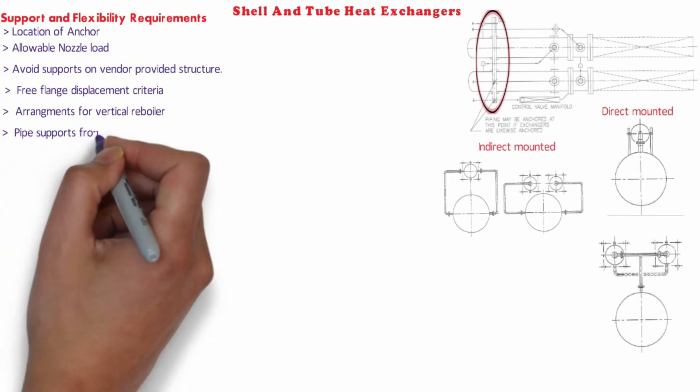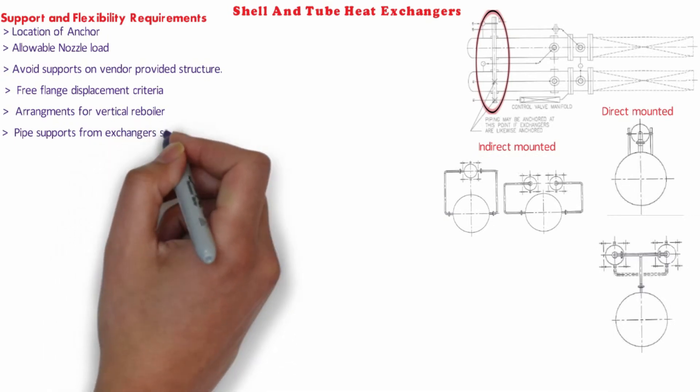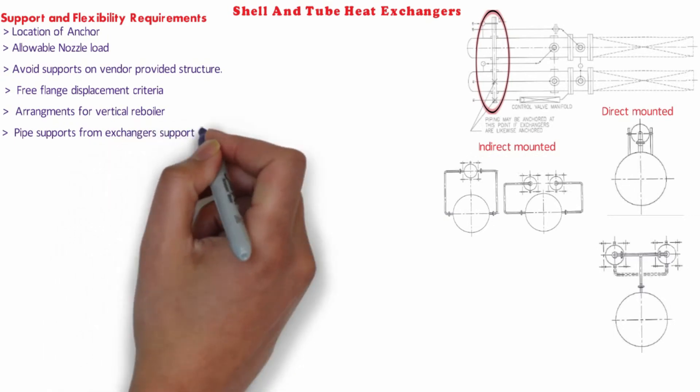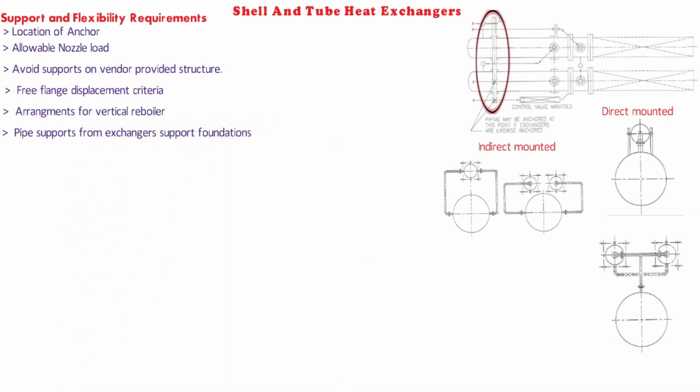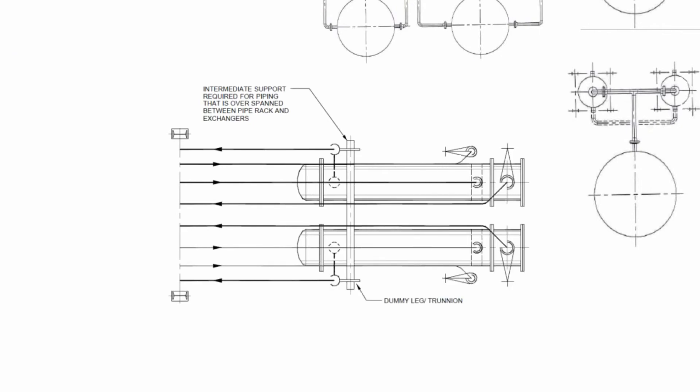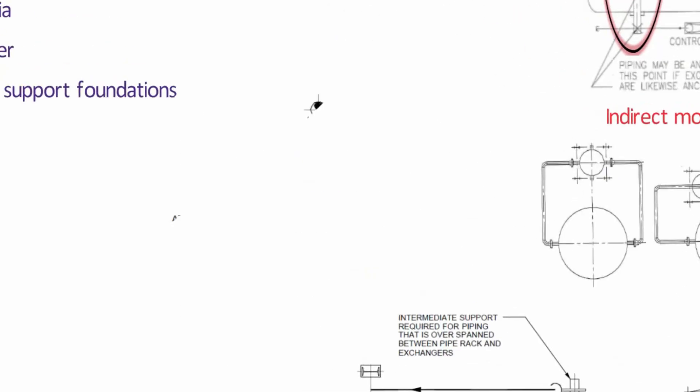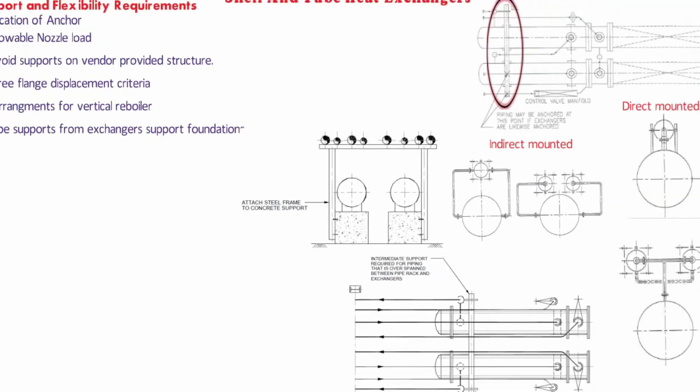Generally, pipe supports at shell and tube exchanges can be incorporated with the exchanger's support foundation and can be set upon the same foundation. This can save the expense of separate support foundations. Anchors set on such supports allow the pipe to grow with the exchanger instead of against it. However, stress recommendations and project specification shall govern this criteria.